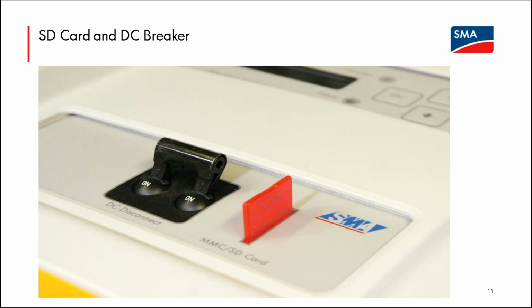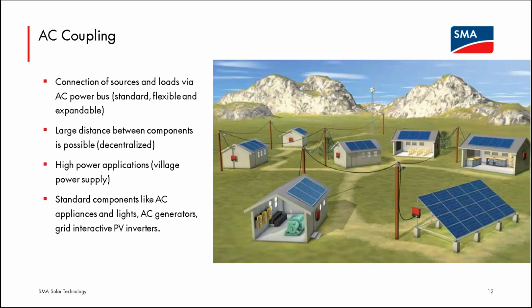The SD card right next to that, we provide SD cards for the devices. It is critical that the SD cards stay in the master. It logs all of the information of as many Sunny Islands as there are in the group at the master. And this is critical. If you ever need to call SMA service, every Sunny Island install is different. And unless service has that SD card information, it is near impossible for them to be able to quickly troubleshoot a system. But with that SD card information, it is pretty straightforward. So always install the SD cards, and there's no reason not to have them installed on all of the devices. We provide them to you.